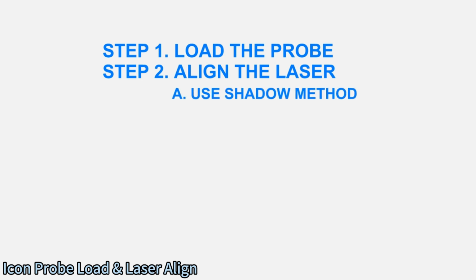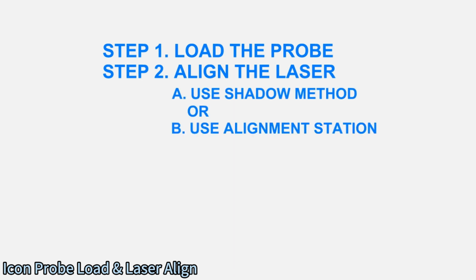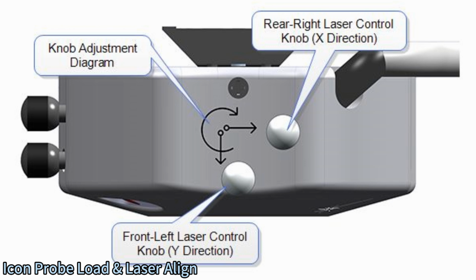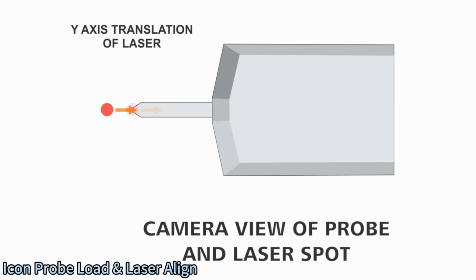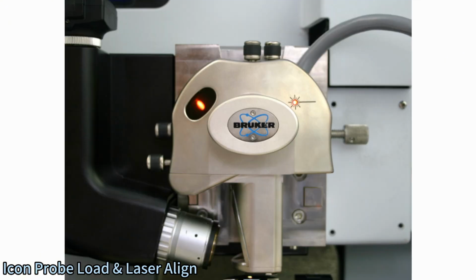There are two methods for aligning the laser onto the probe. Either method can be used to position the beam. The first technique involves projecting the laser onto a surface underneath the head and probe holder to observe the beam as it moves across the cantilever. The two knobs on the top of the dimension head are used to adjust the position of the laser onto the probe cantilever. On the left side of the head, there are two knobs to adjust the reflected beam onto the photodetector.